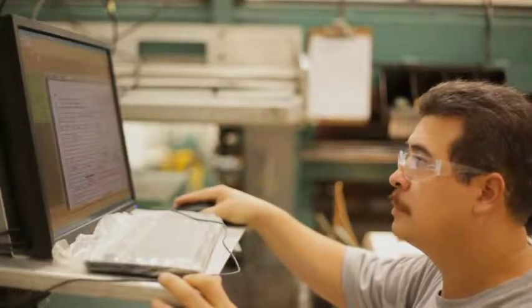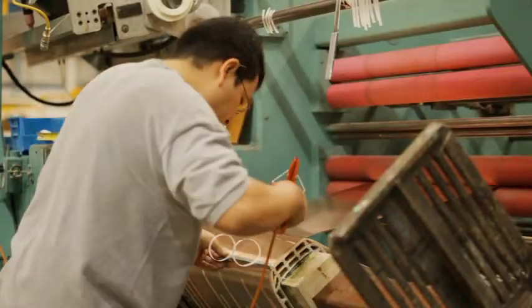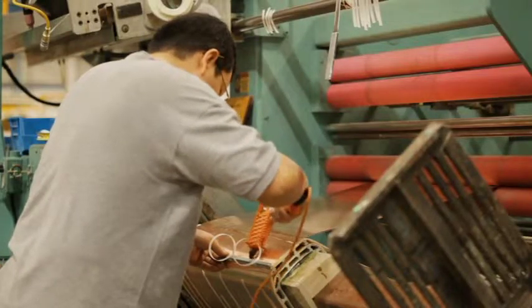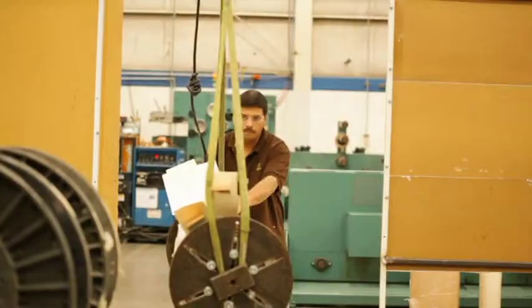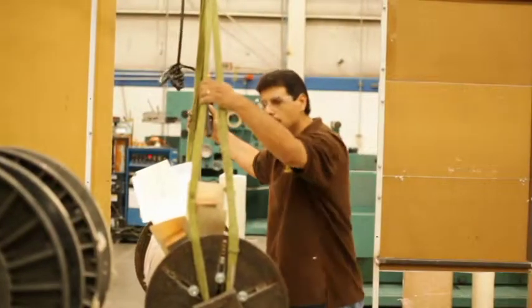The low voltage winding inspection process verifies that important parameters of the coil, such as the number of turns, perimeter, diameter, as well as welding terminals to the sheath, are within the ranges calculated by the engineering and design areas, using quality methodologies such as zero defects quality and effective inspection. The process continues with the high voltage windings.